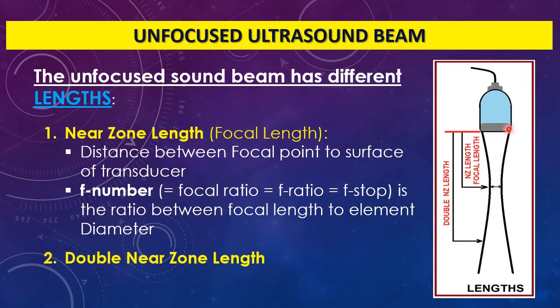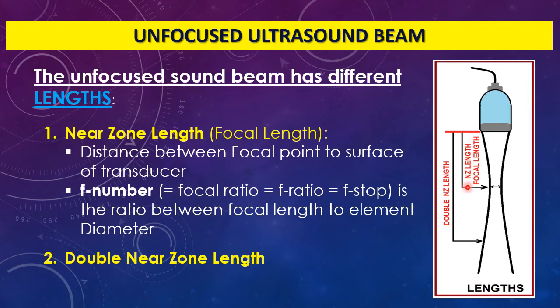Another length to discuss is the double near zone length. If the near zone length is, say, 10 centimeters, the double near zone length is 20 centimeters. The beam continues beyond this point, but at the depth of double the near zone length, a specific event occurs. The near zone length is related to the F-number, which is the ratio between the near zone length (or focal length) compared to the diameter of the ultrasound beam.